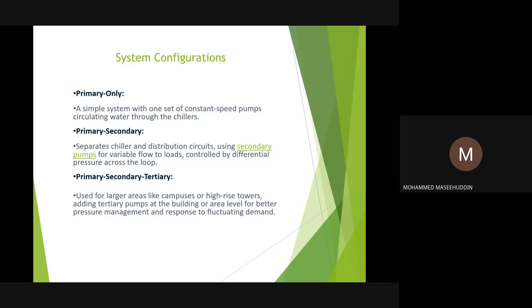Then there is another circuit as well for high-rise buildings. You know that when there is a high-rise building and there are huge malls and everything, these kinds of buildings and malls require another circuit of pumps, which is called tertiary pumps. They are installed to boost the water from the point where the secondary chilled water pump ends, to the last point in the building. So tertiary pumps come into play mostly, 90%, with high-rise towers. Buildings of, let's say, 80, 85 stories or 70 stories do require these kinds of circuits.